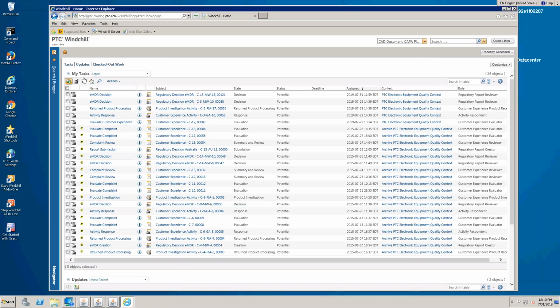So now the only thing left to do at this point is to go through and submit this to the FDA. If that's once again something that you have to go in and do, then yes, this is now the step that you will go through and take. If you didn't have to submit it to the FDA, then at this point, you're done. That whole process is now complete. So you've gone through and you've documented any injuries that were sustained, any issues with the machines. You've gone through and evaluated the machine.